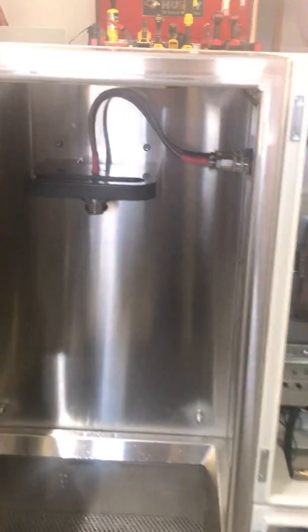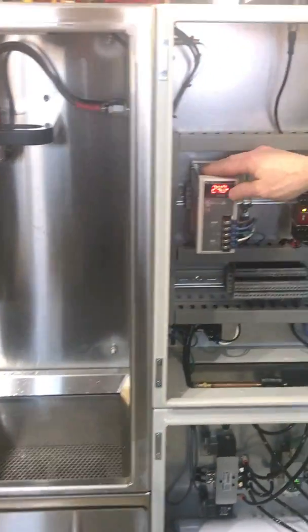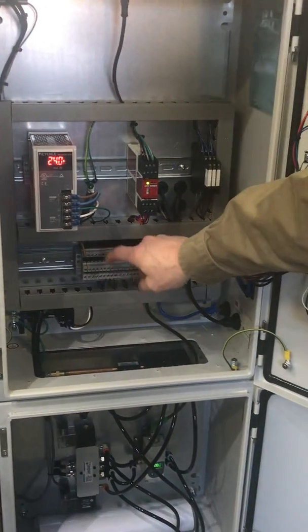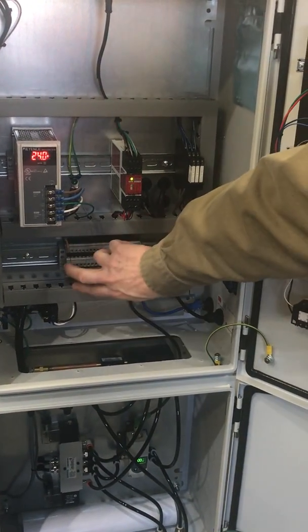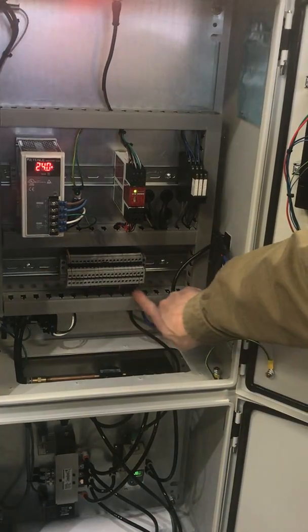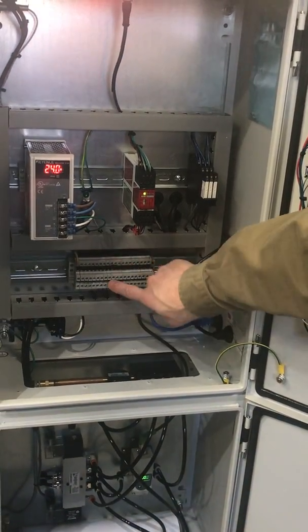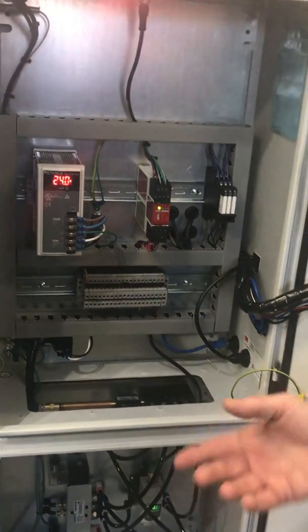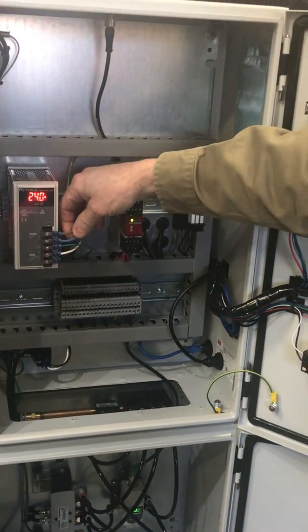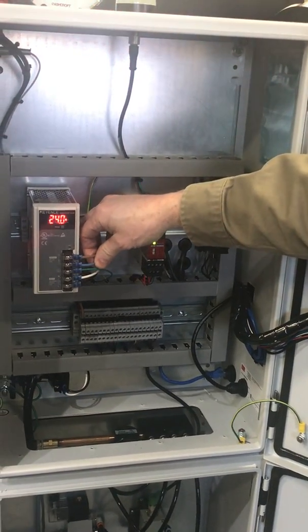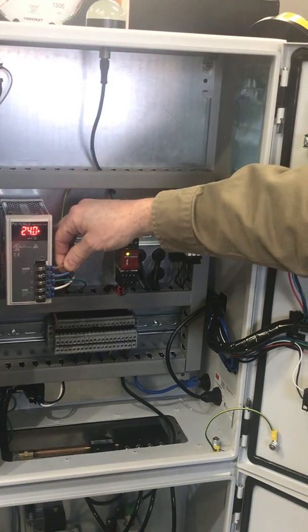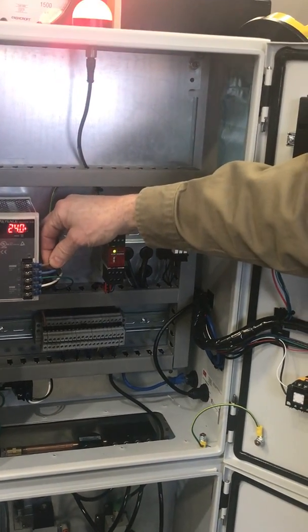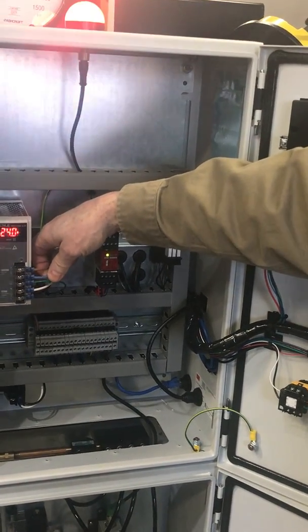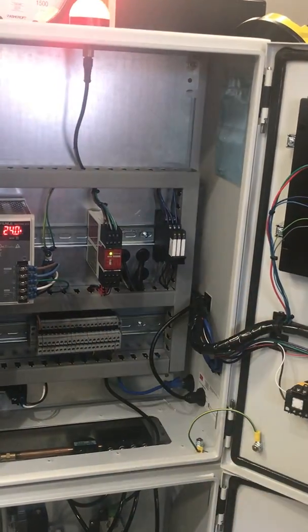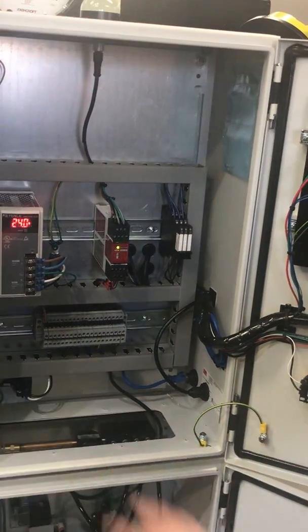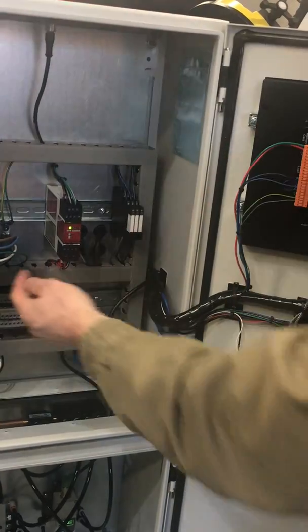You gotta be kidding. So what happens here is there's your power, 24 volts. It floods this thing. So the bottom one is 0, the top one is 24. So we run everything it needs, hot and cold or 0 and 24, into that. We're using the European standard. Brown is hot, blue is not. So if it overheated and smoked, it would turn brown. That's hot. And blue is as safe as the sky. Okay. So that's your blue. I don't know why it's European, but all the sensors and everything you buy nowadays, they all run that same thing. So there's your line in.